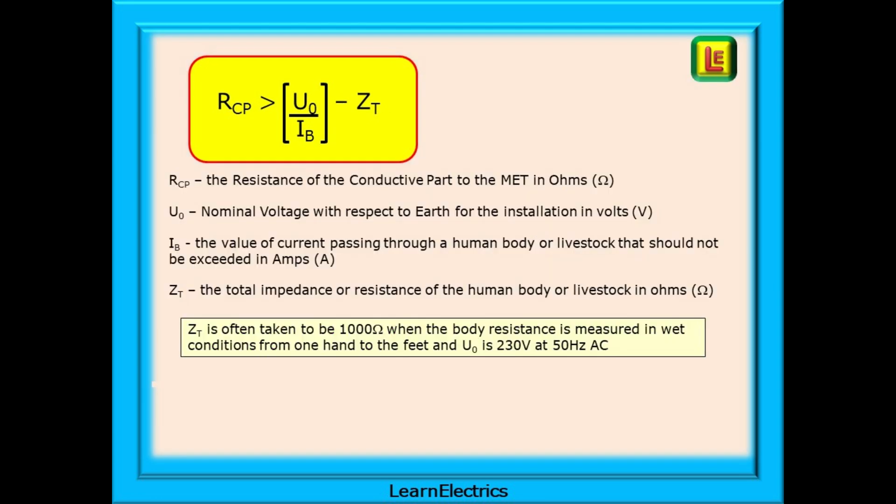If we break this formula down, we realize that this is just Ohm's law using different letters. RCP is the minimum resistance between the conductive part and the main earth terminal in Ohms. U0 is the nominal line voltage with respect to earth for the installation in volts. And IB is the value of the shock current that is passing through a human body or livestock that should not be exceeded in amps. And the designer will decide what this maximum figure is.